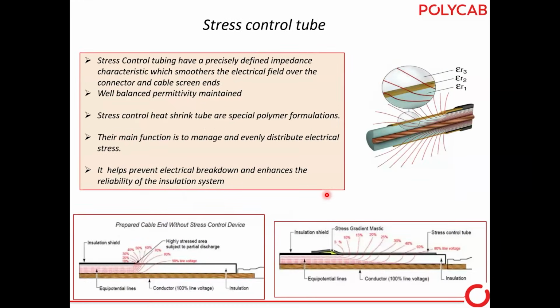Let's see the next, the stress control tube. This is very important in any cable joints and terminations. Whenever you go from 11 kV to EHV, the stress control tube, or in EHV we say the stress cone, is very important. If the stress control tube is not of quality standard, the joint or termination will definitely start failing early. So the design of the stress control tube is very important. Its impedance should be precisely defined. It is a well-balanced parameter.